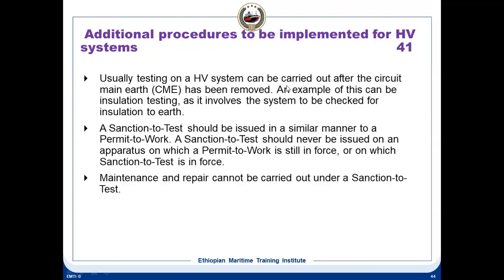Usually testing of the high voltage can be carried out after the circuit earth has been removed. An example of this is insulation testing, as it involves the system being checked for insulation to earth. See, you are grounding a switchboard for working. Suppose you want to do a Megger test or a PI test, you need to remove the ground. So the grounding is not always done.